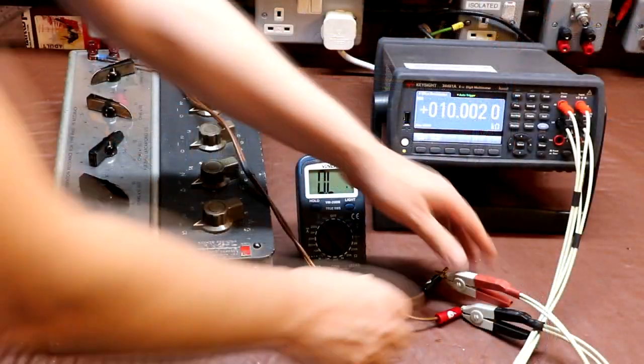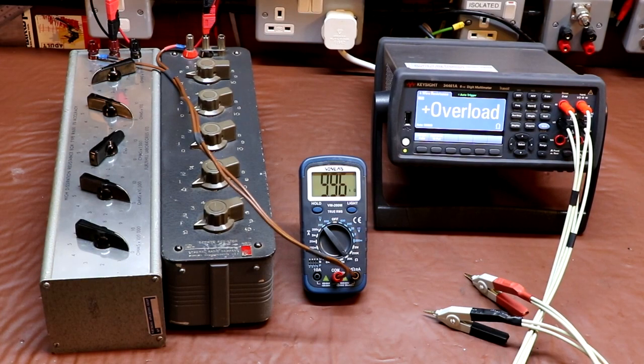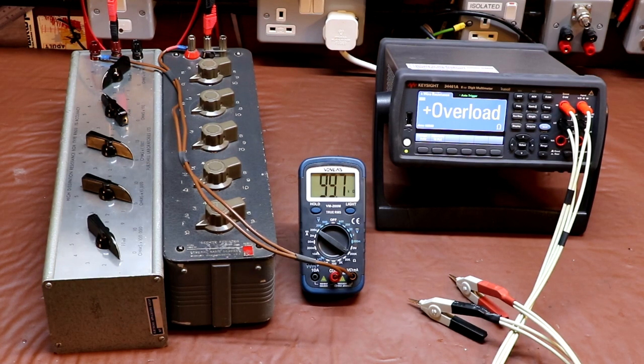With 100 ohms set on the 200 ohm resistance range we're 0.5 of an ohm under. With 1 kilo ohm set on the 2 kilo ohm resistance range we're low by 4 ohms. With 10 kilo ohms set on the 20 kilo ohm range we're 40 ohms under. With 100 kilo ohms set on the 200 kilo ohm range we're 300 ohms under.